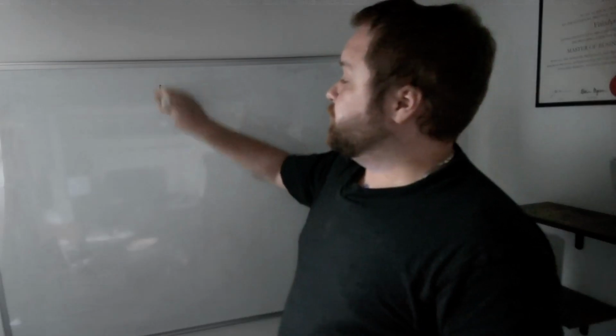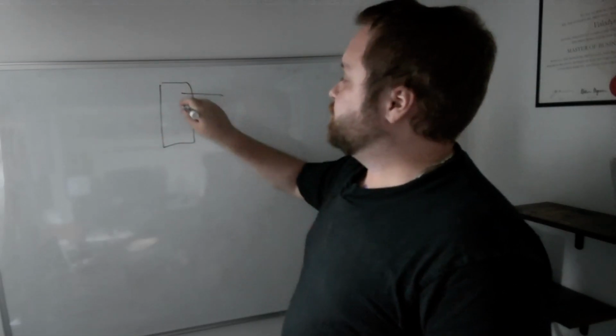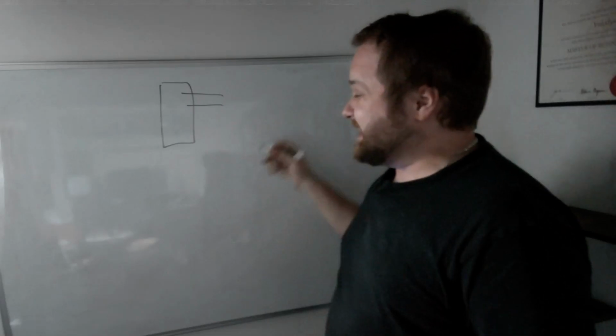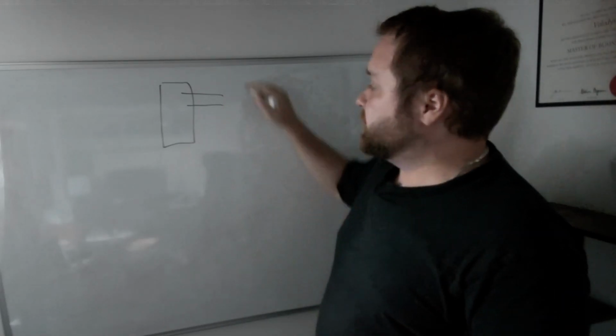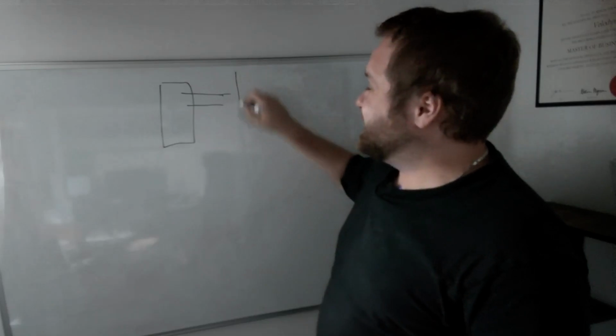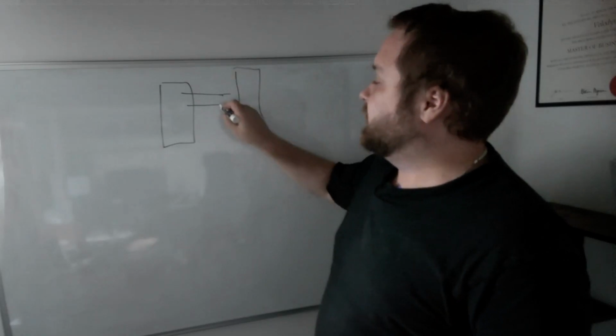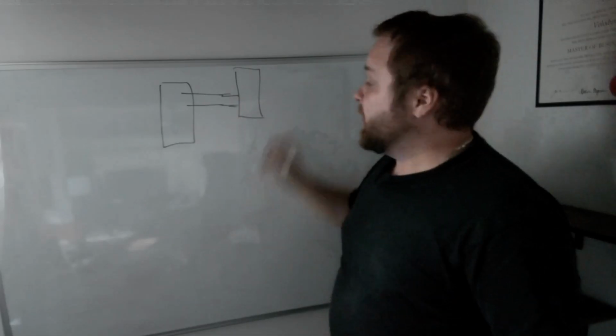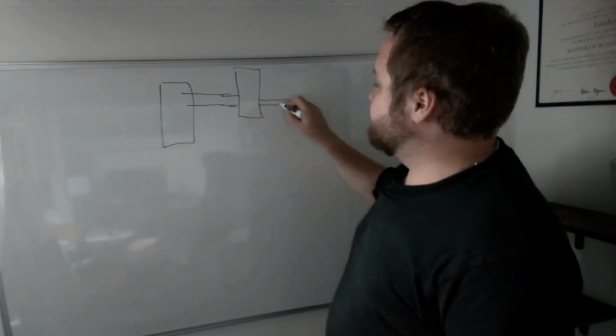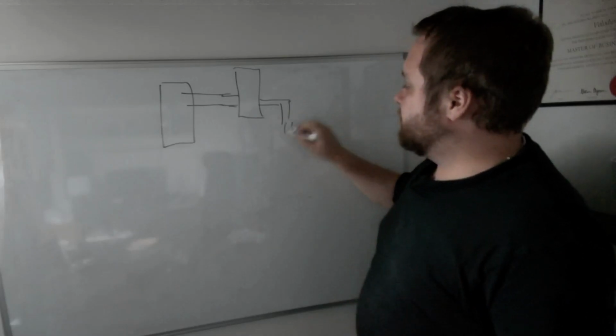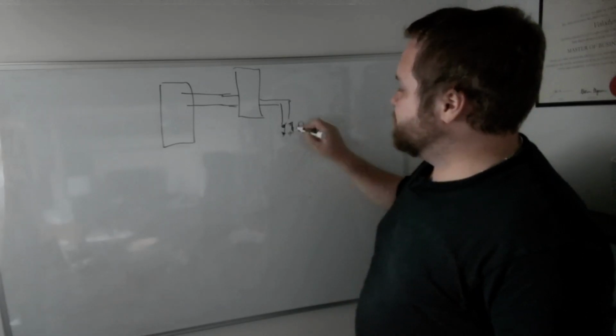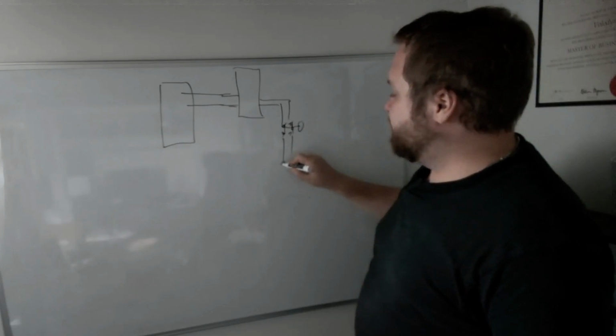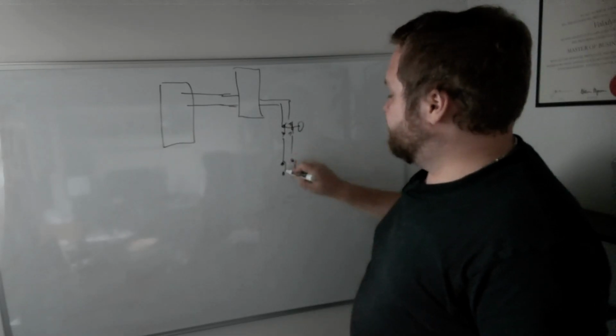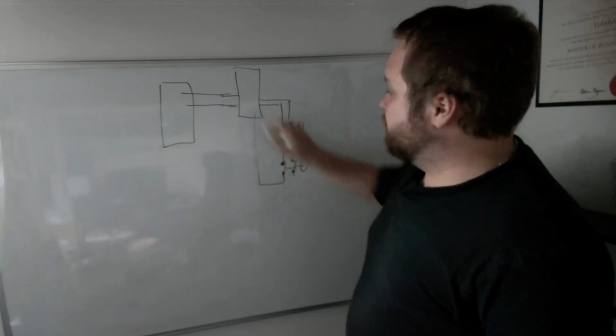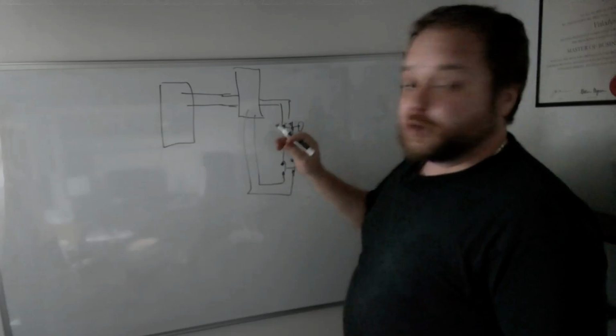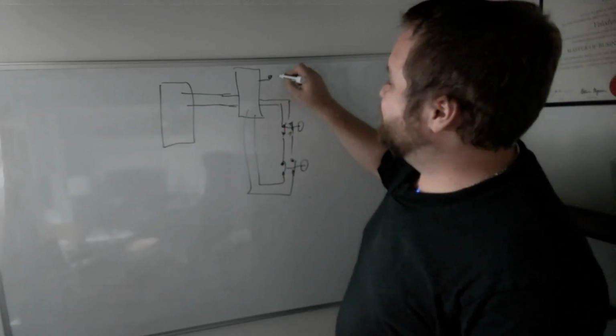So like we discussed, you can have a relay which is going to output two signals that are going to be checked by the inputs for dual channel safety. What is possible for you to do is to create a chain of relays. So here I'm going to have a second one, which is going to basically consume these signals, and it's going to emit its own circuit. So here I'm going to have a set of e-stops, right? So this is going to be a set of, again, push buttons, and my drawing is not going to be very pretty, but hopefully you understand the concept where you have a push button here, and then this is going to go back into this specific relay. And so here I'm going to have, for example, a push button to reset the circuit.